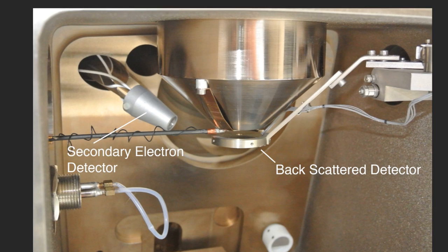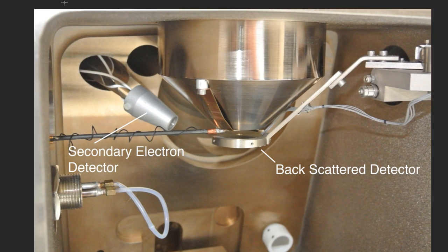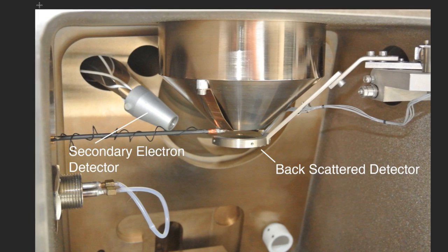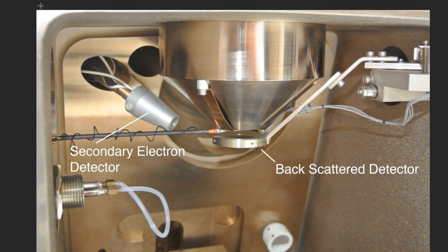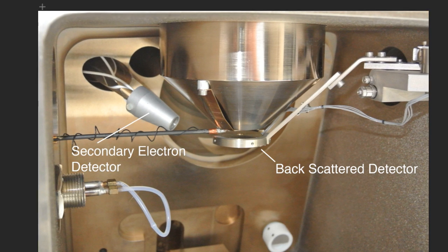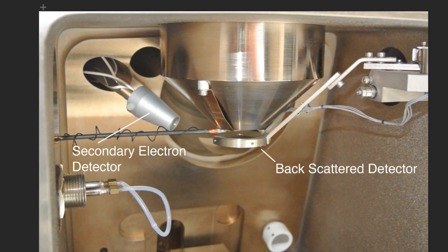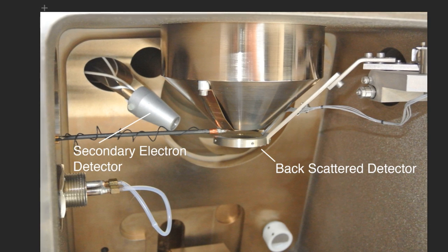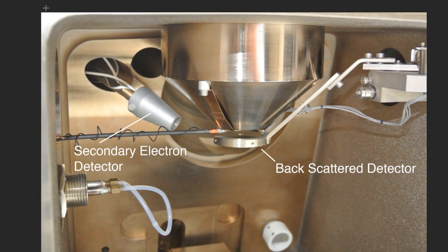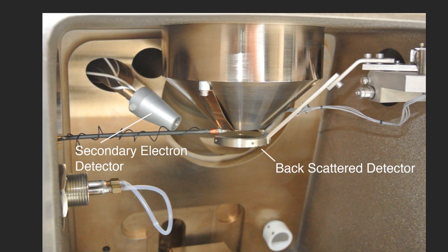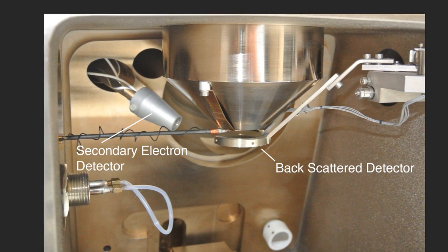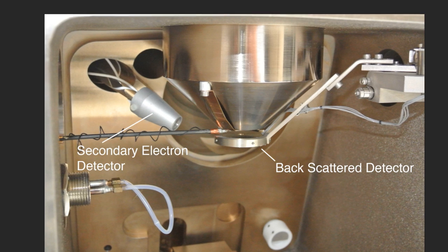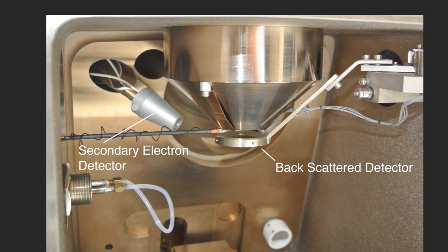Inside my machine, it's got two different detectors. It's got a secondary electron detector there on the left, and the center where the beam goes right inside or through the backscatter detector. There's two different locations for these detectors, so each of these images gets a little bit different view of the sample. And this is true at the lower magnification. Not so true once you get really high magnifications, maybe above 2,000 or 3,000x. So I'm going to go through this procedure, and we'll figure out how this whole thing works.